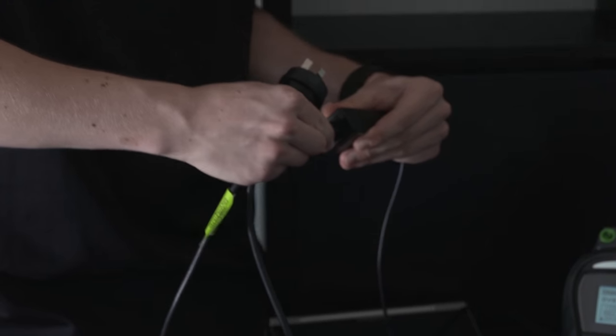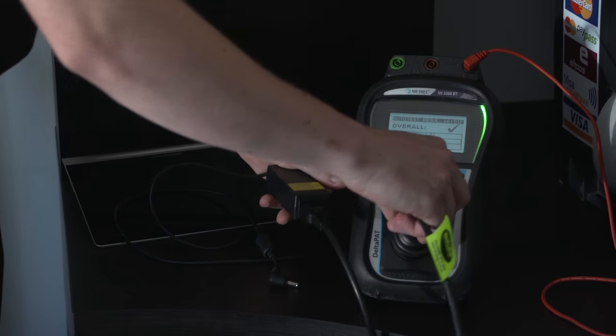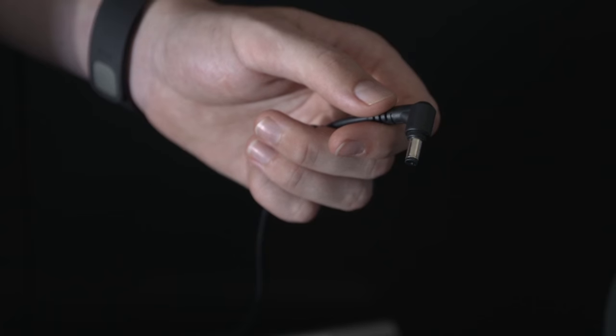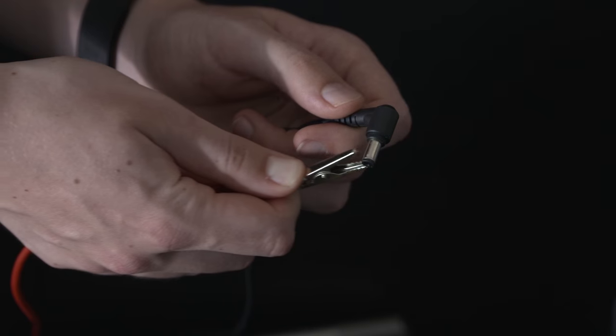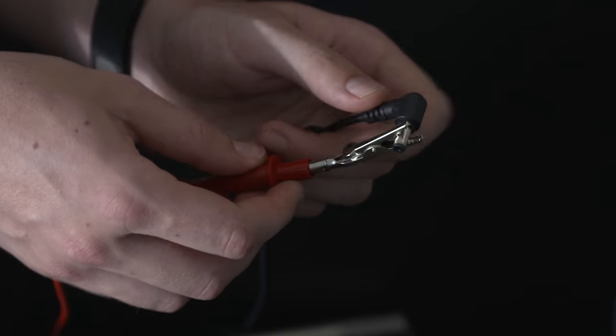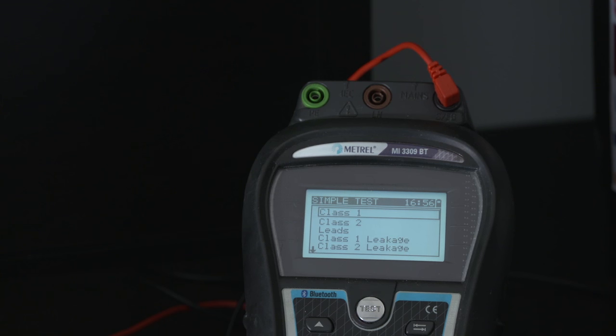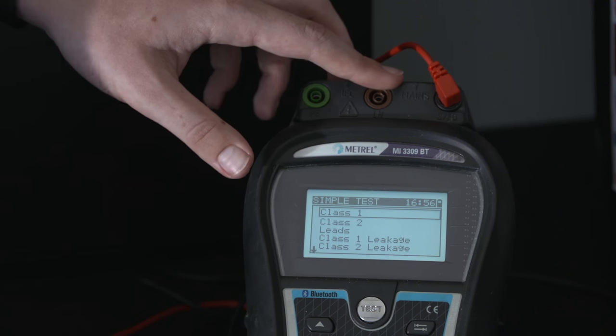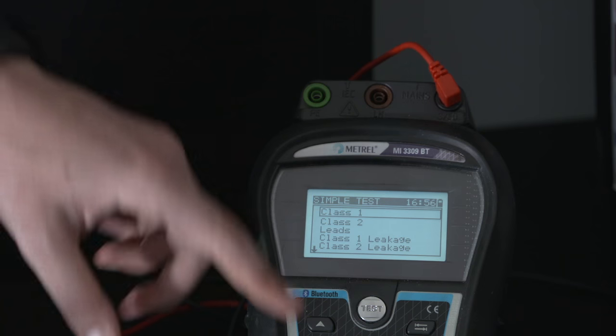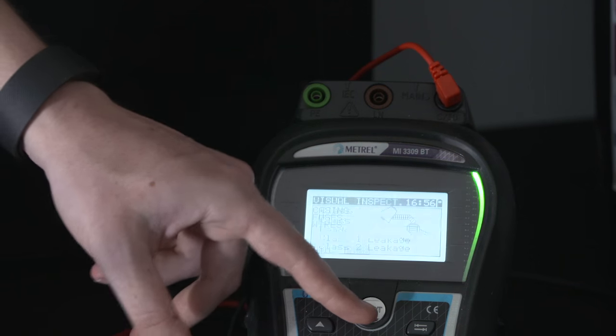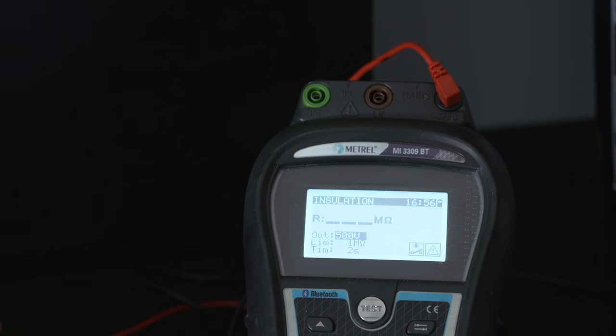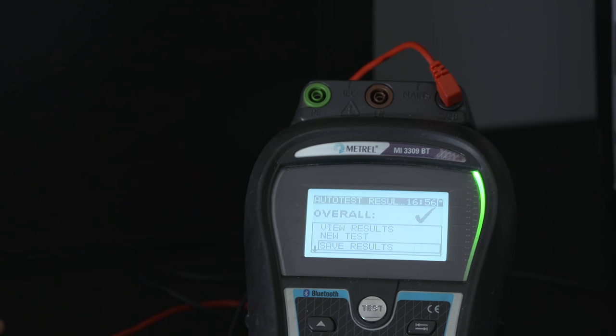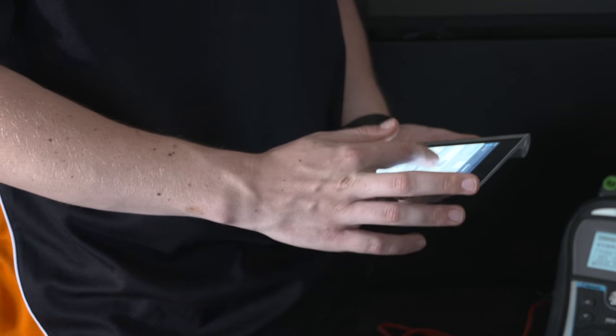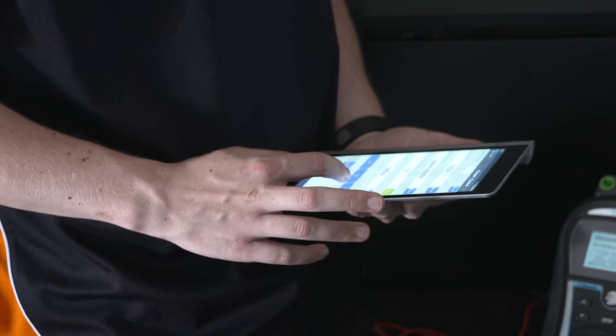If the IEC lead passes, we'll then move on to the second part of the test. I'll reconnect it to the power adapter and plug the plug into the front of the PAT tester and attach the alligator clip to the exposed metal part on the end of the plug. The alligator clip is connected to our tester via the red lead. We are now ready to run a Class 2 double insulated test. As we did before, we'll enter the details and print off a tag.